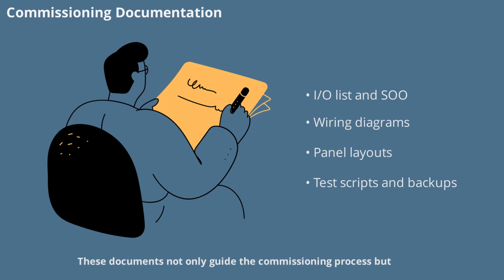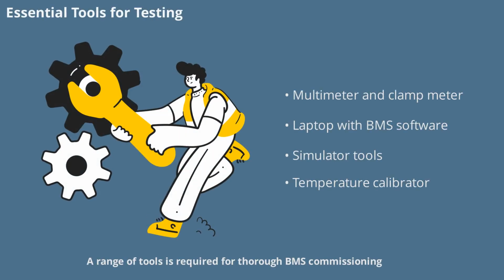These documents not only guide the commissioning process but also serve as a reference for future maintenance and troubleshooting. A range of tools is required for thorough BMS commissioning. Multimeters are used for voltage and continuity checks, while clamp meters measure current draw. A laptop with BMS software is essential for programming and diagnostics. Simulator tools such as Modbus or BACnet browsers help test communication. Temperature calibrators and hand pumps are used for validating analog inputs and pressure sensors. Having the right tools ensures accurate and efficient testing.